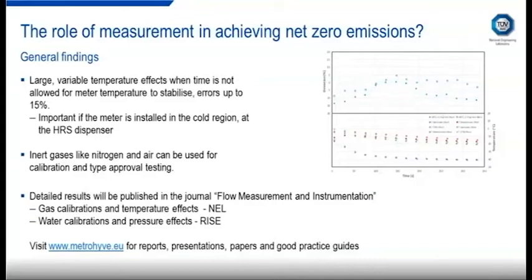So what we can see is that over the course of 5 minutes or so, as the temperatures began to stabilize, we saw errors ranging from -15 up to +5%. So those are very large. And this has important implications for the hydrogen refueling stations, because if the meter is installed downstream of the heat exchanger, it could be exposed to this effect. So this is one more thing that has to be accounted for, and it really shows the importance of assessing the hydrogen refueling station as a complete measurement system.